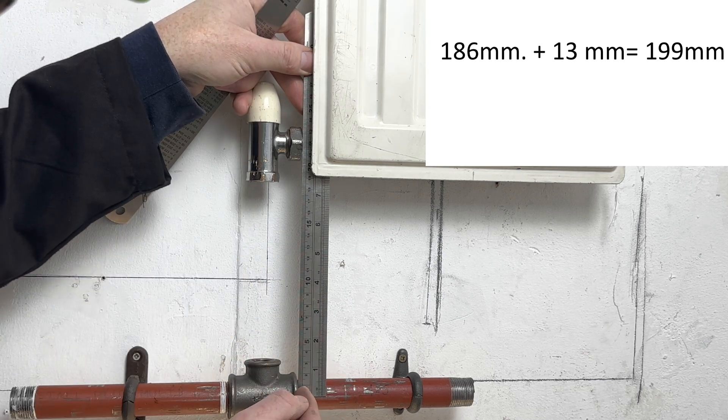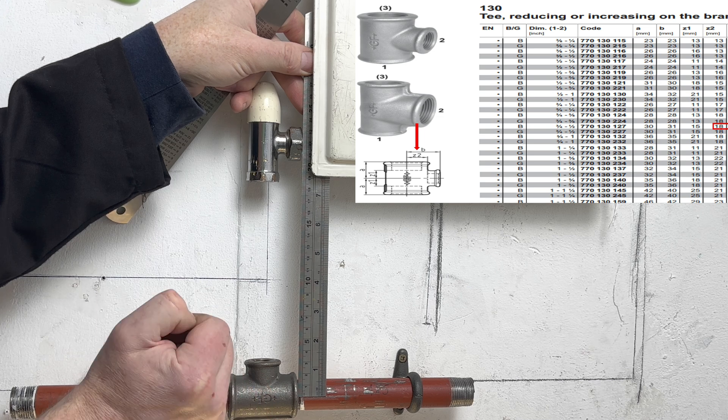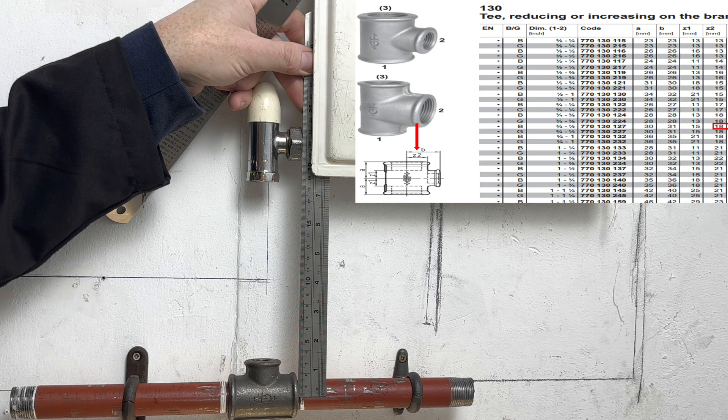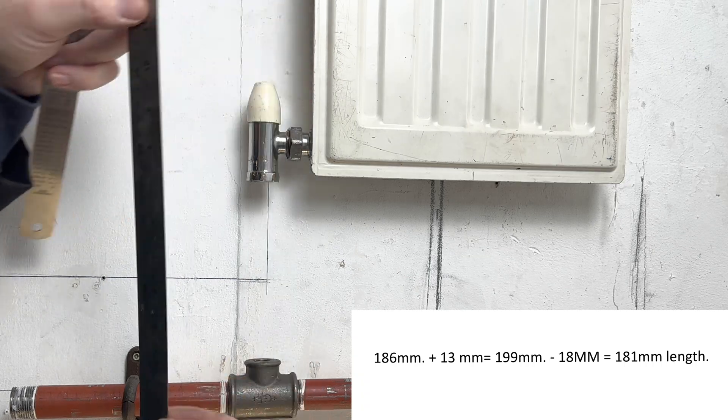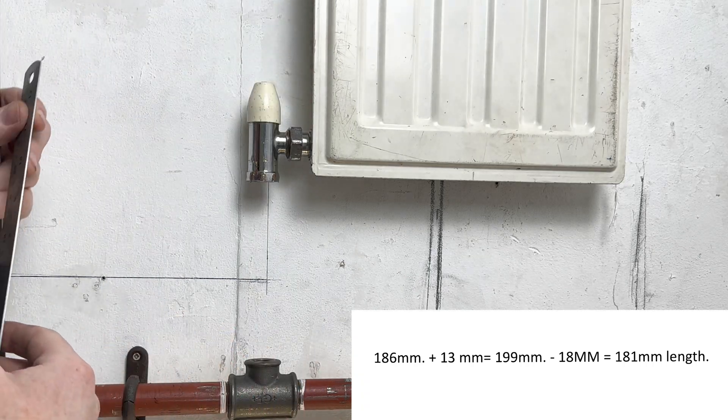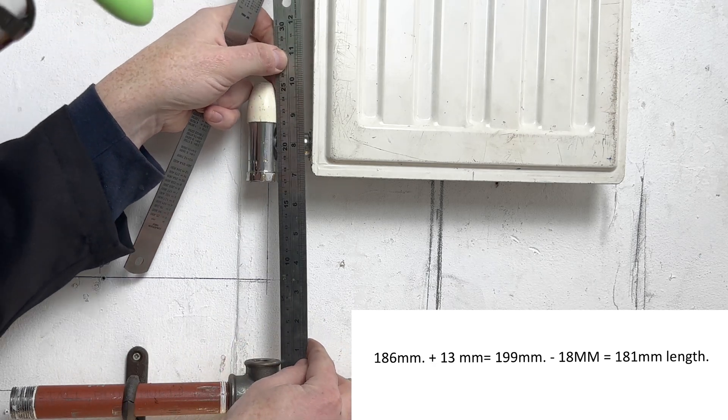And we then take off the Z dimension, from here to here, which is 18mm. So 199mm minus 18mm equals 181mm is the pipe length.